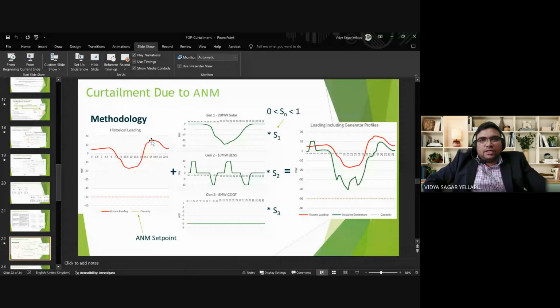Positive values are taken as demand values and negative values are generation values, because at times there is little demand in the local distribution network and there is a lot of generation in the local distribution network. So that has to go to the upstream. So in that case, it will be negative here. And this is the rating of the asset, minus 50. It is the power profile of a solar plant of 20 megawatts in size.